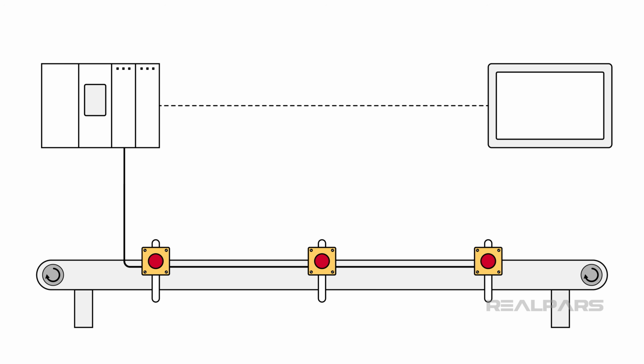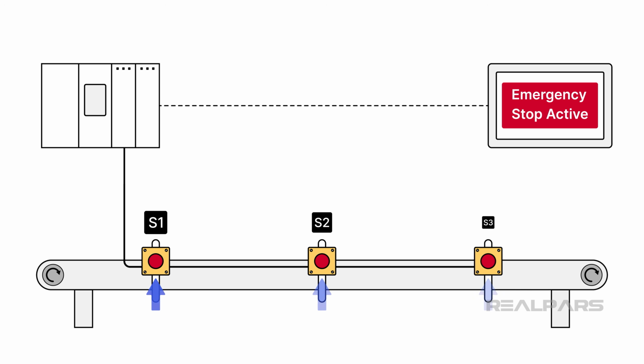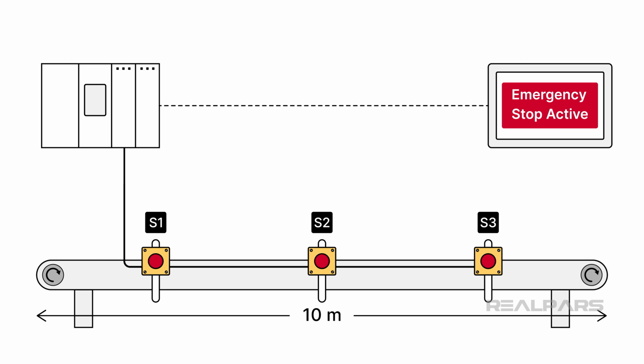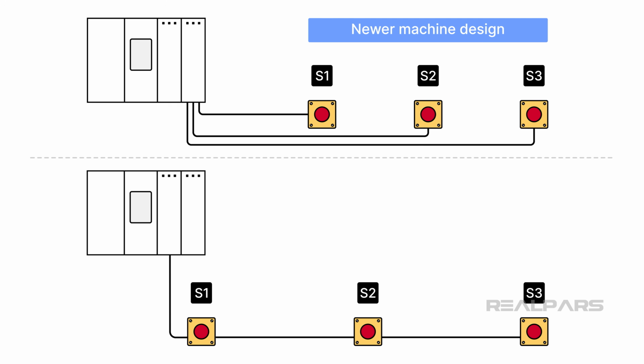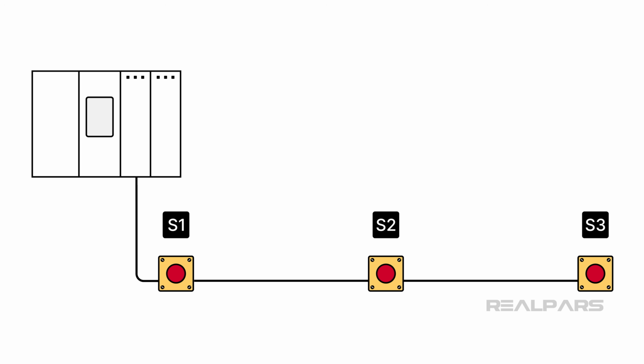You're the guy who's just been given the nod to find out why the production line has come to a screeching halt. The operator reports an HMI flashing fault reading Emergency Stop Active. Here's the interesting part. There are 3 e-stop buttons at different locations along a 10-meter conveyor system. You know from experience that the 3 switches are wired in series, and the fault alarm can't tell you which switch is causing it. Newer machine designs use separate safety inputs for each e-stop, but for a number of reasons, your plant does not use them.